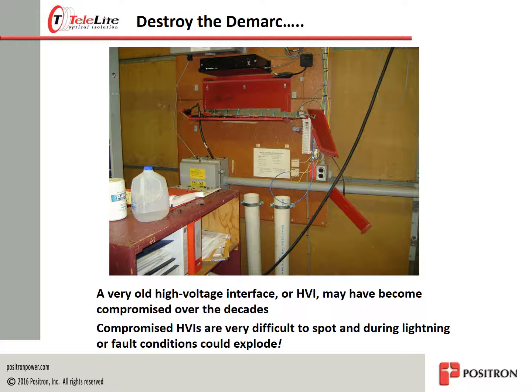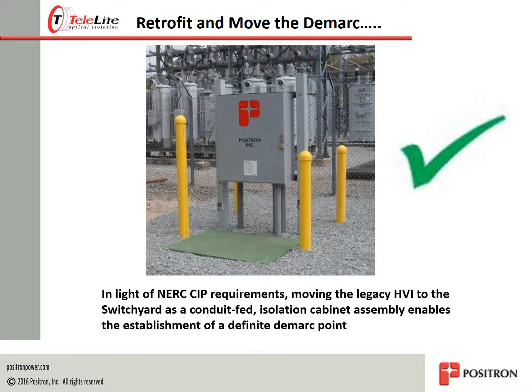Unmaintained high-voltage interfaces that have been subjected to many GPR events can weaken over the decades. This subject has not received the attention it deserves, though. Having an old HVI that poses a risk inside the substation control house is counterintuitive to securing the bulk electric system cyber assets. Establishing a new demarcation facility with a new outdoor cabinet HVI assembly mounted on an H-frame inside the switchyard is a key enabler to NERC CIP security requirements compliance. As specialists in GPR and HVIs, Positron can help you renew the high-voltage interface and establish a demarcation point that lends itself well to NERC CIP requirements.